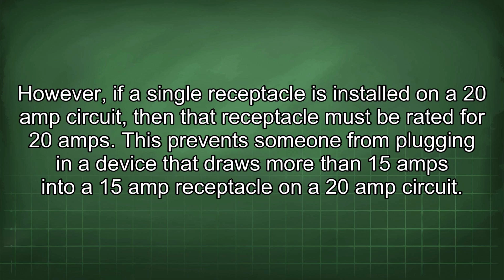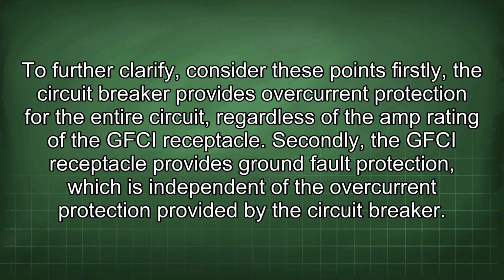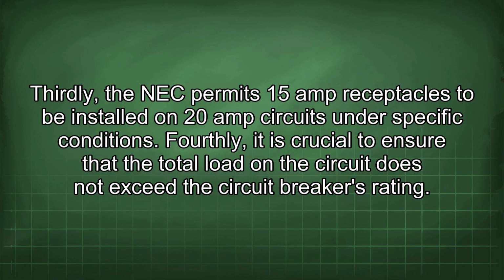However, if a single receptacle is installed on a 20-amp circuit, then that receptacle must be rated for 20 amps. This prevents someone from plugging in a device that draws more than 15 amps into a 15-amp receptacle on a 20-amp circuit. To further clarify, consider these points. Firstly, the circuit breaker provides overcurrent protection for the entire circuit, regardless of the amp rating of the GFCI receptacle. Secondly, the GFCI receptacle provides ground fault protection, which is independent of the overcurrent protection provided by the circuit breaker. Thirdly, the NEC permits 15-amp receptacles to be installed on 20-amp circuits under specific conditions. Fourthly, it is crucial to ensure that the total load on the circuit does not exceed the circuit breaker's rating.